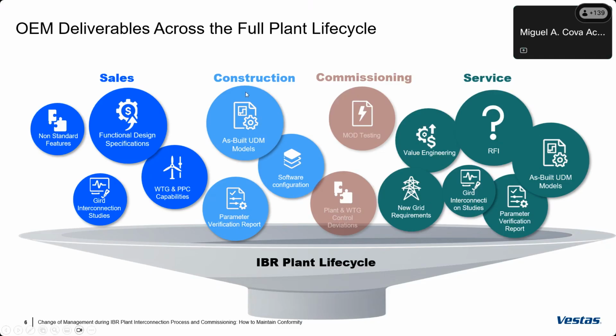During construction, we move toward as-built models based on the grid interconnection studies. We update the software configuration, because as I said, the sales phase could be 3-4 years before actual construction, when different software was running for the power plant controller or turbines. We then produce the first parameter verification report, which links back to the earlier presentation, ensuring the grid interconnection studies and the actual product on site match one-to-one. This is fundamental, and I know some markets in the US have started requiring this. We run this parameter verification process for every site, not just as a deliverable to the operator, but as a sanity check to ensure everything is right.